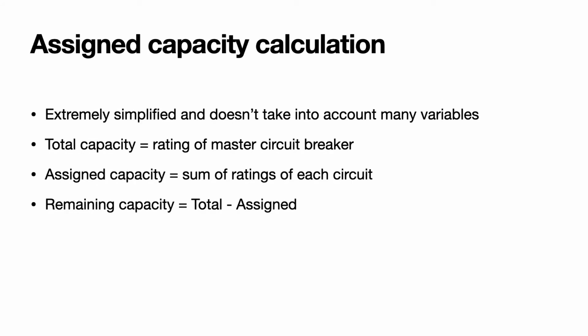Let's talk about the calculation we did outside at the service panel. What we did was calculate what I'm calling assigned capacity. Now this is an extremely simplified calculation, and it doesn't take into account many variables, but the calculation is fairly straightforward. The total capacity is the rating of the master circuit breaker. So we're assuming that the master circuit breaker was properly sized to match the sizing of the wire going from the utility and also the capacity available through the local transformer. The master circuit breaker will fit within that capacity.